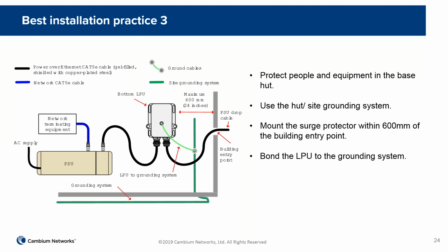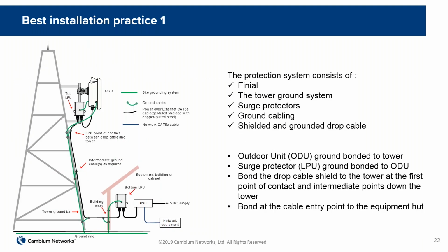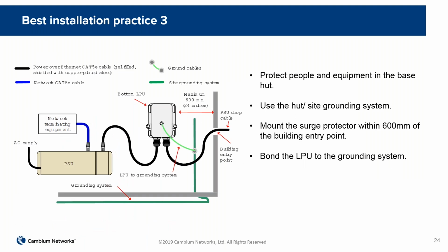It takes the surge to ground, and just popping back a moment, we'll have grounded the screen of that cable before it enters the building at the building entry point just here, to make sure that the outer doesn't carry significant energy into the building. The energy is fed to ground before it gets into the building. And then the cores of the cable, any energy that remains on those, is carried to ground by the LPU inside the equipment hut to the local ground system within the hut.